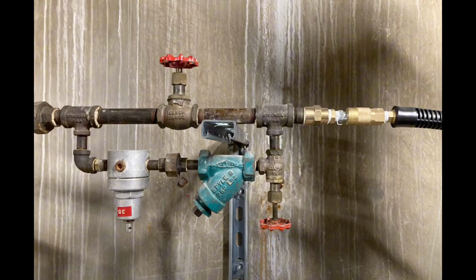So here's where we're going to install the air pressure sensor. We have our air compressor sending air to this piping that supplies air to our dry fire sprinkler system, and we want to monitor the air pressure. If the air compressor ever fails, or there's a pressure drop because we develop a leak, we want to know about it right away. If the air pressure drops too much, the valve could open and flow water into the sprinkler system or start dumping water out the drain, and that could trigger a false fire alarm. We don't want to do that.